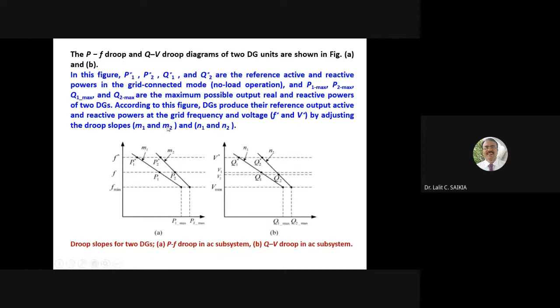For DG1, the frequency versus P curve is like this, and for DG2 it's like this. Similarly for the V versus Q curve, N1 and N2 are the slopes. By adjusting these slopes, we can regulate the DG to produce the reference output at the grid frequency and voltage F star and V star, by adjusting M1, M2, N1 and N2.